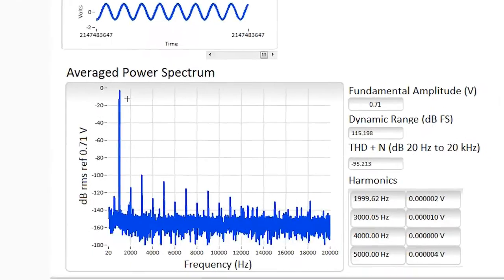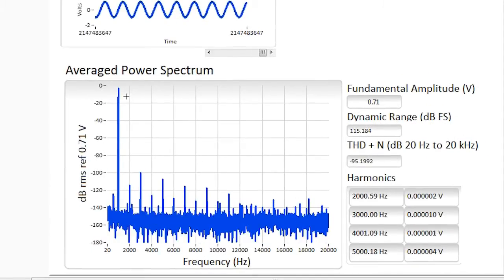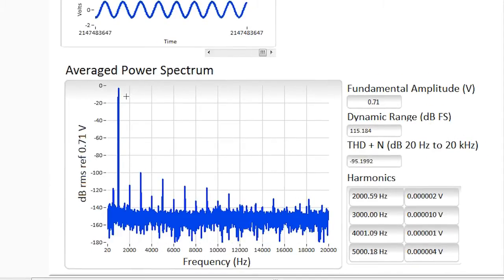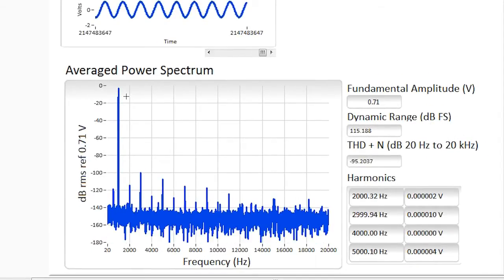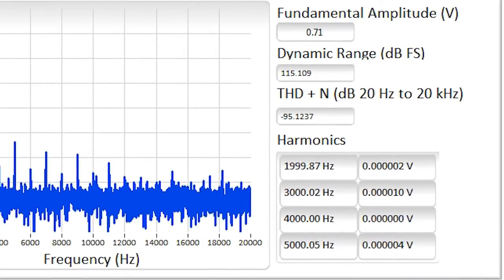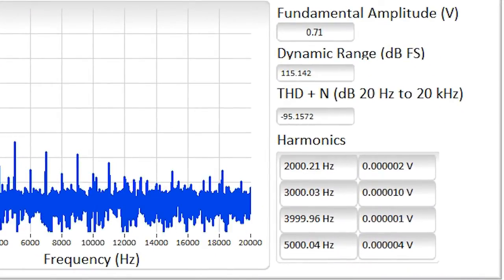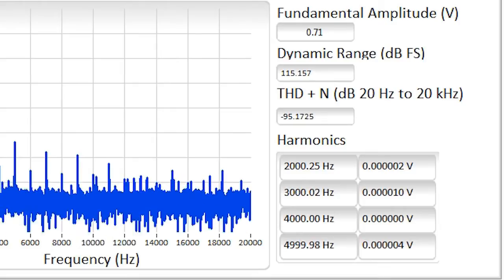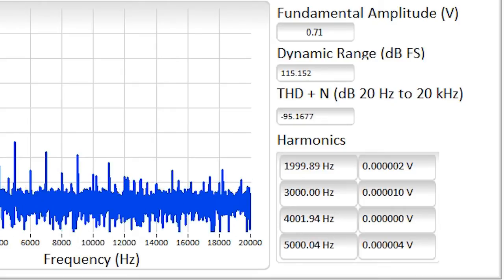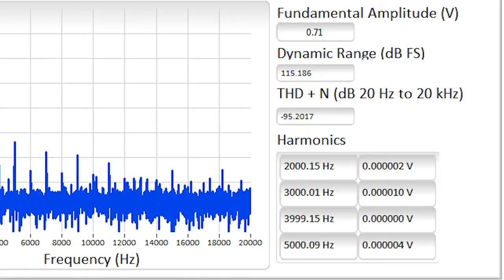If we go to the software, you can see that I have a time domain signal. I'm generating a sine wave — it's a 1 volt sine wave — and you can see the spectrum here below. This is allowing me to take metrics like fundamentals, dynamic range, THD plus N, and you can actually see some of the harmonics that I'm analyzing as well. These metrics are typically used for verification tests in labs, as well as final production line tests.